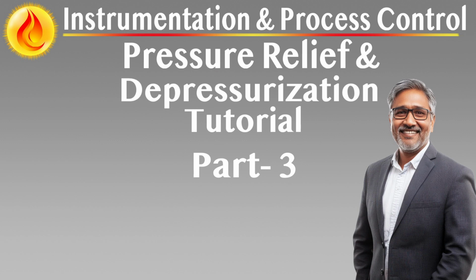Emergency depressurization systems. General principles. Relief valves are designed to protect against pressure excursions by releasing limited amounts of process fluid. However, they cannot effectively reduce pressure throughout an entire system or vessel. In high-risk scenarios, such as fire exposure or major leaks, emergency depressurization becomes essential to quickly reduce internal pressure and prevent rupture, escalation, or boiling liquid expanding vapor explosion, BLEVE.